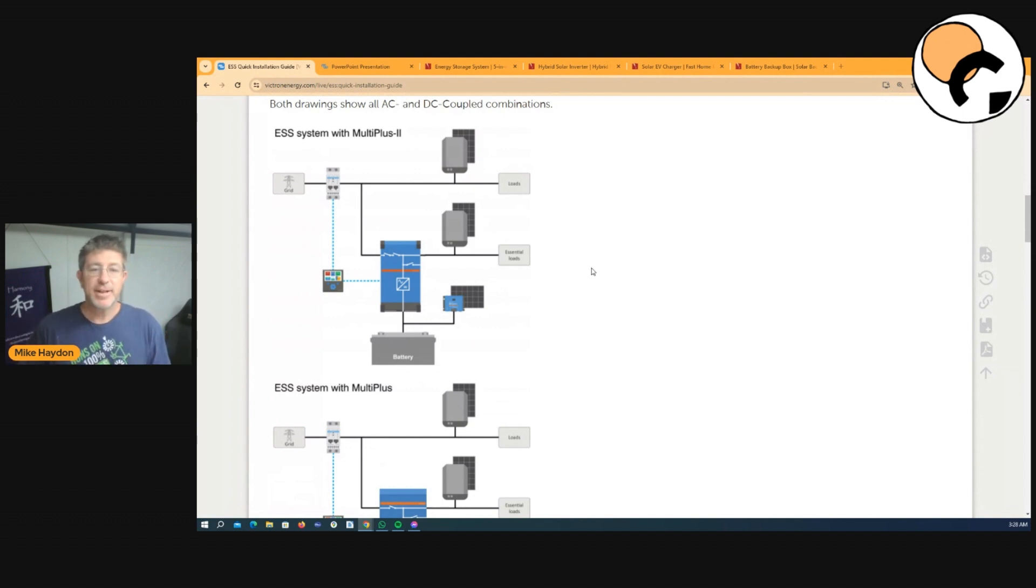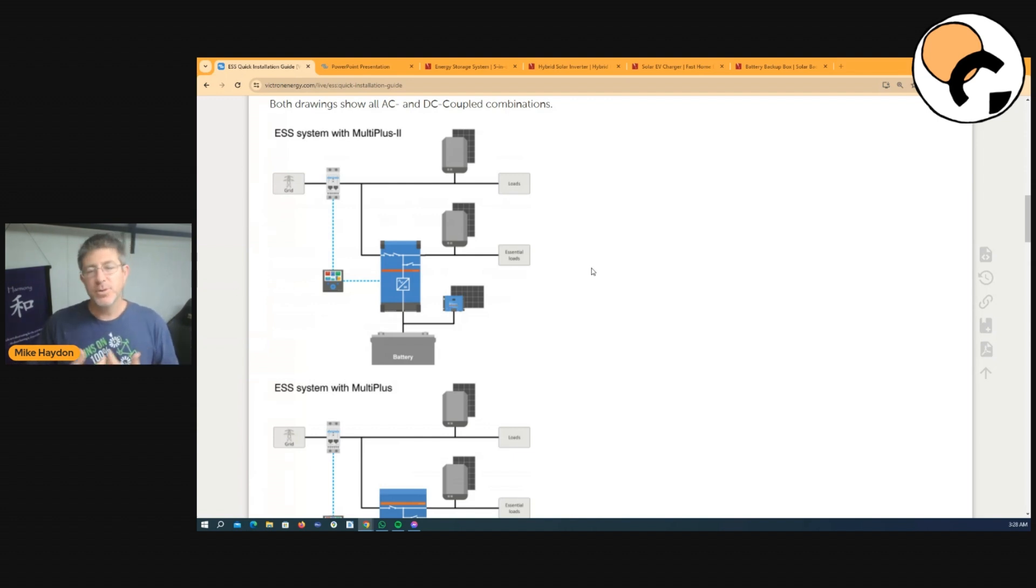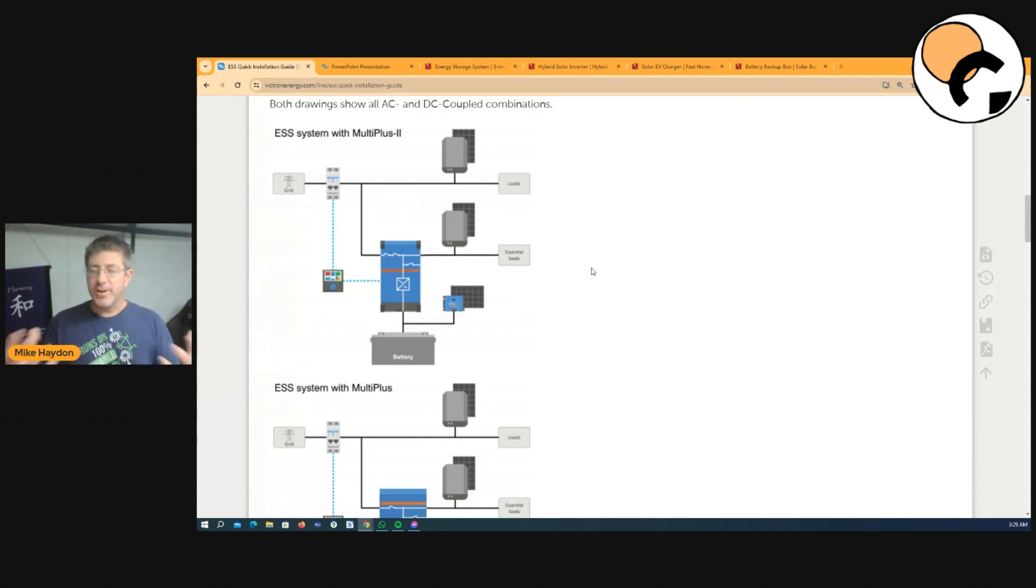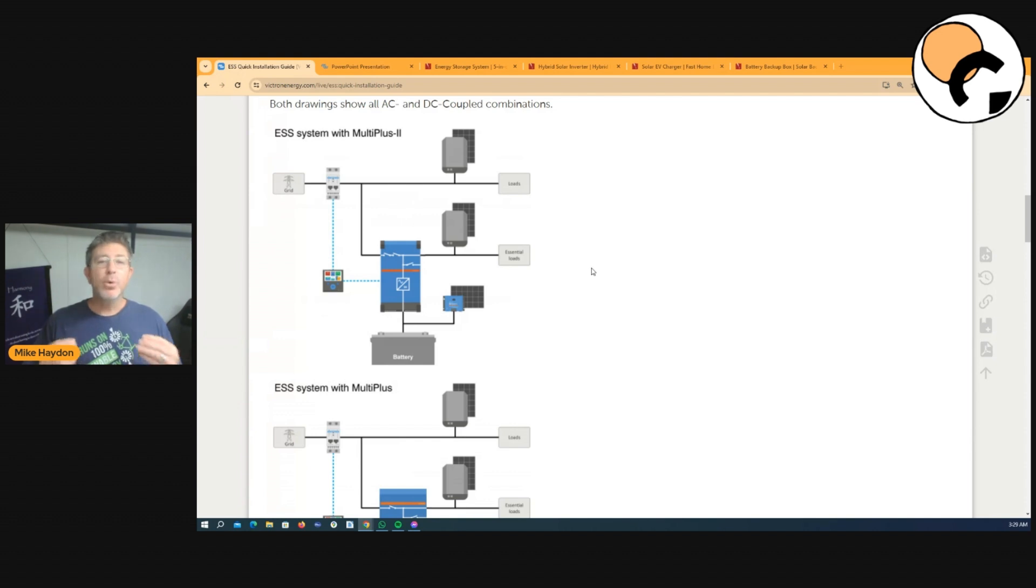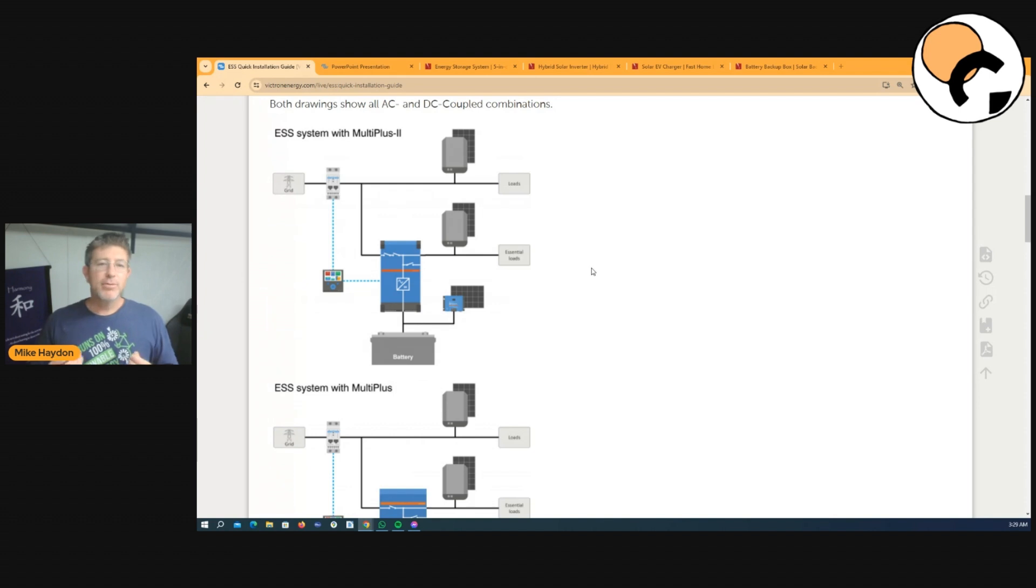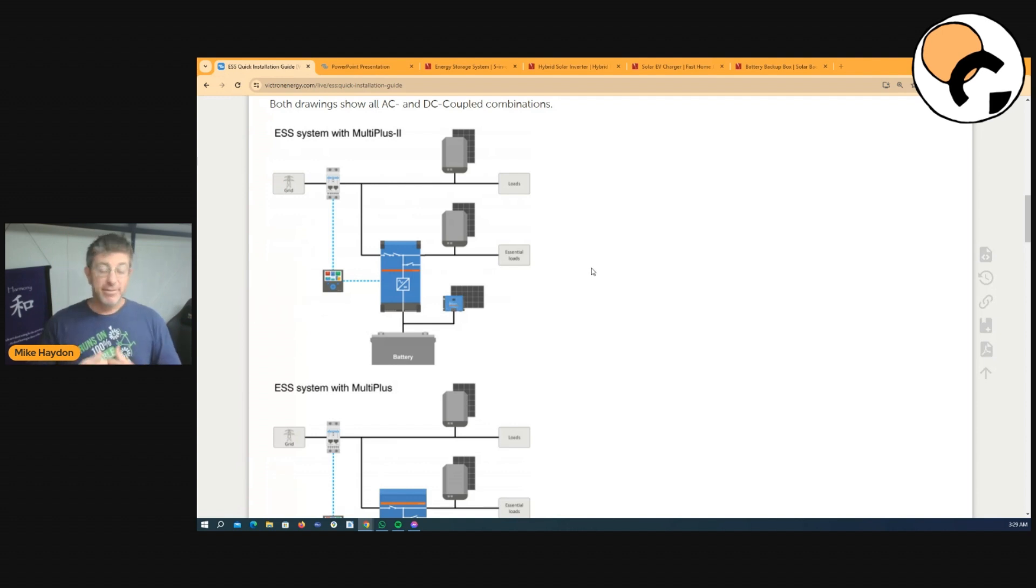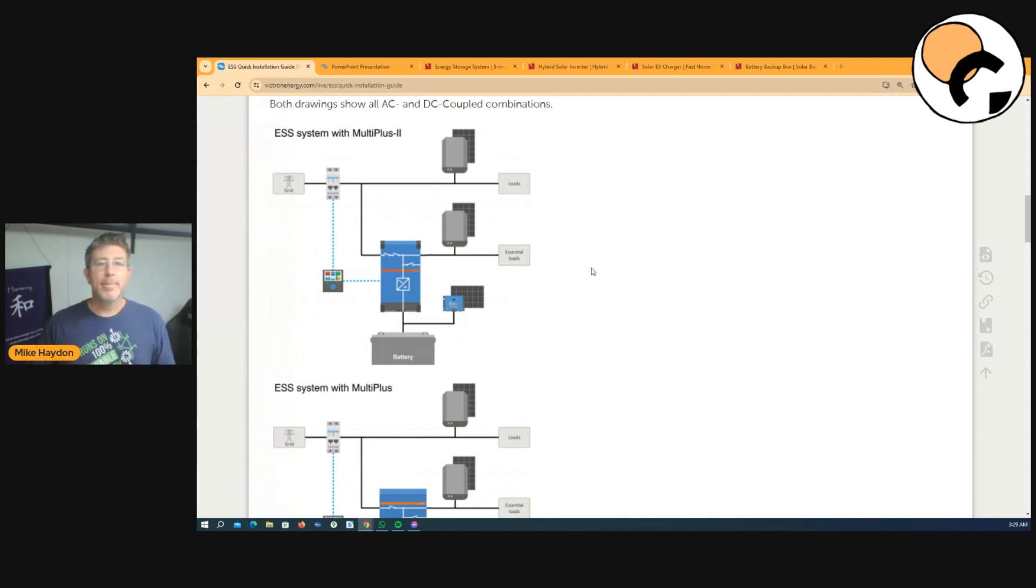One of the big foundation problems with Victron is actually design principles. This is not something I suppose no one's ever thought about this. It's not just Victron themselves, but the way an off-grid system works in the way it's designed. And this is more for parallel and bigger systems. A lot of people over the years have dealt with wanting multiple inverters. So they want to have two inverters or three inverters in a three-phase situation from Victron Energy. The problem when you have multiple inverters in a system, people think it's going to be more reliable. That is true. But if one fails, we still require to reprogram it. So if you get two inverters and one fails, we still require to reprogram that inverter when it does fail.